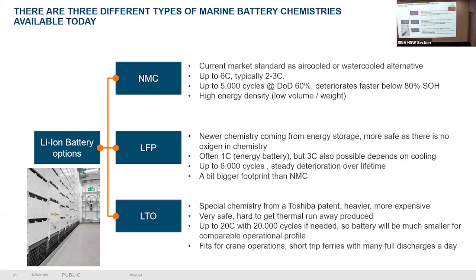Then we have another chemistry called LTO, again gaining popularity, lithium titanate oxide. It's a special chemistry patented by Toshiba and manufactured by a battery maker based in Sweden, Echandia. Expensive, but very safe, and it is hard to get thermal runaway because the chemistry is much more stable. It can go up to 20C, with a high number of cycles. So the battery will be much smaller for a comparable operating profile, obviously.